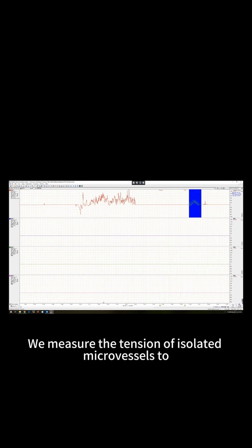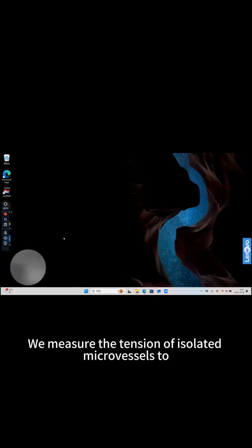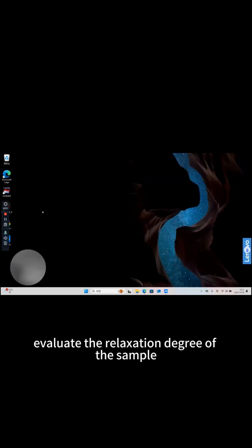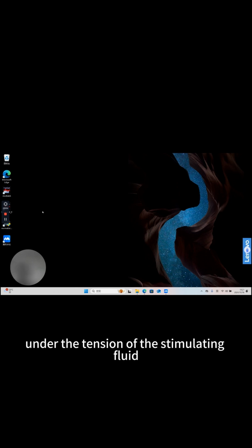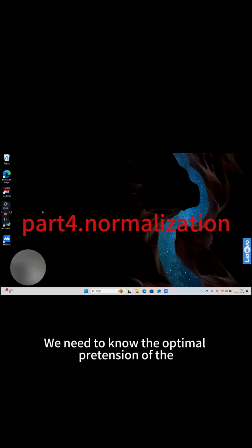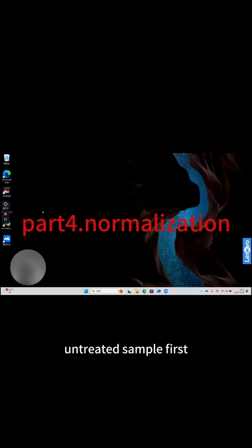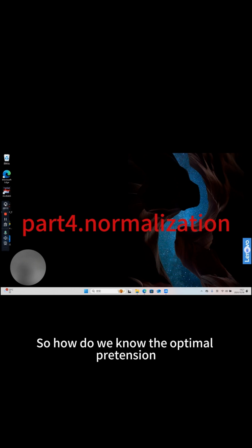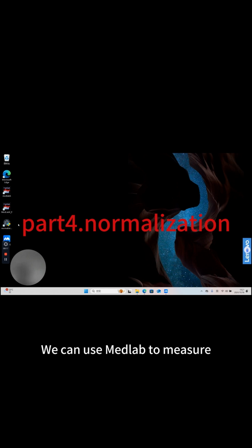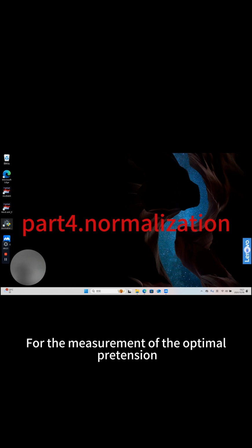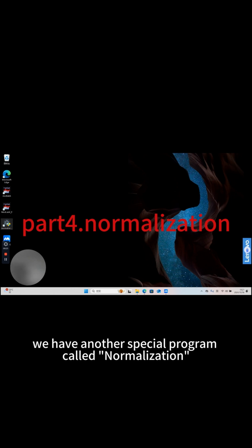We measure the tension of isolated microvessels to evaluate the relaxation degree of the sample under the tension of the stimulating fluid. We need to know the optimal pre-tension of the untreated sample first. So how do we know the optimal pre-tension? We can use MATLAB to measure the approximate preset tension. For the measurement of the optimal pre-tension, we have another special program called normalization.